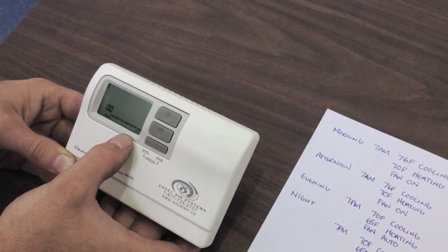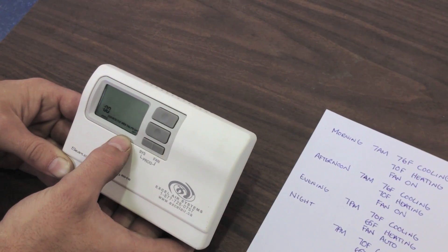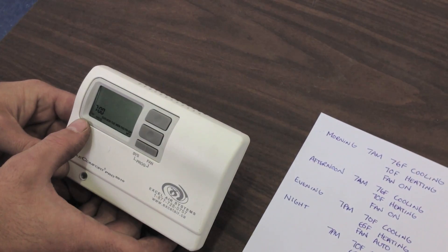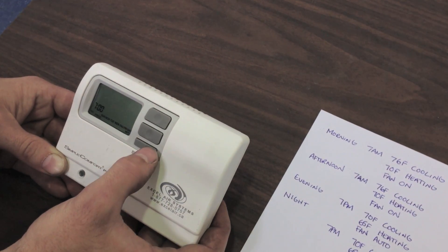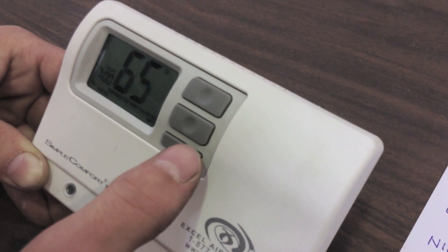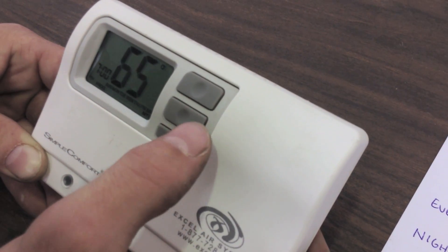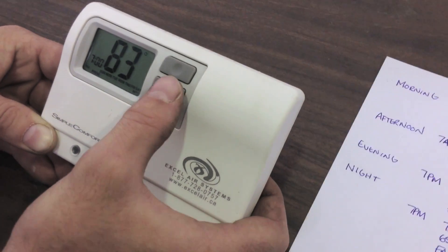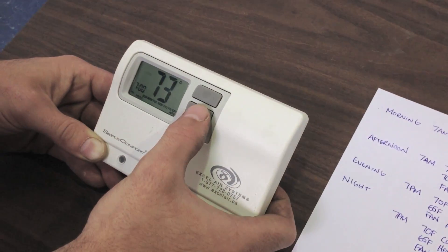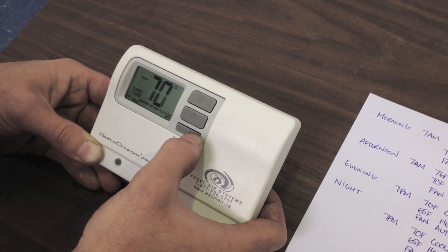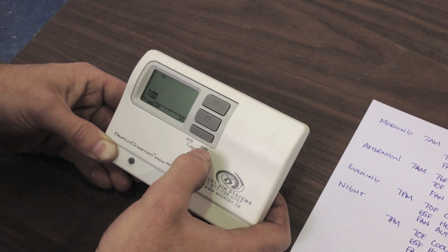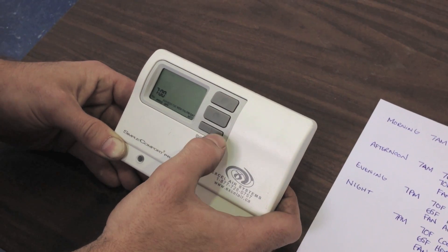And we're on our last schedule, our night schedule, which we're going to duplicate the evening by going down to 7 p.m. Make sure p.m. is displayed. Push fan. Pass our minutes fan one more time. We're going to go to our heat set point of 65. We push fan again, our cool, which we want to go to 70 degrees. We push fan again when we're happy. And our fan we want in the off position. And we push fan one more time.